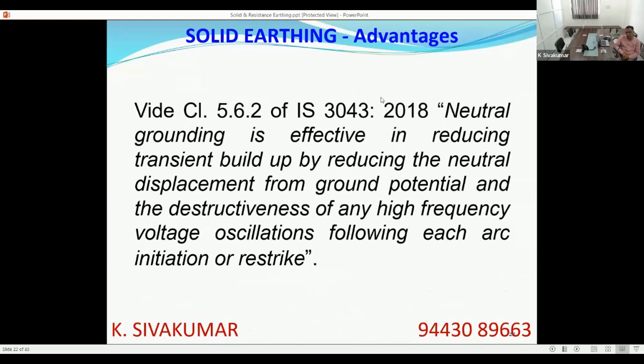And transient voltage buildup. We saw that the neutral to ground voltage will be raised to phase voltage, because in an ungrounded system, whenever one phase gets grounded, the ground rises to that phase's potential and the neutral is no longer at zero potential. So there is a voltage buildup in the neutral, which we called neutral shift. When you do solid earthing, when you connect the neutral solidly with the ground, this never happens. The ground is always kept at neutral potential, and the neutral is always kept at ground potential. So there is no chance of transient overvoltages in the system, because we saw that transient overvoltages will happen in an ungrounded system. With a lot of diagrams and explanations, I have shown the calculations and formulas for how transient voltage buildup happens in an unearthed system. In a solidly grounded system, the chances of transient voltage buildup are very negligible.